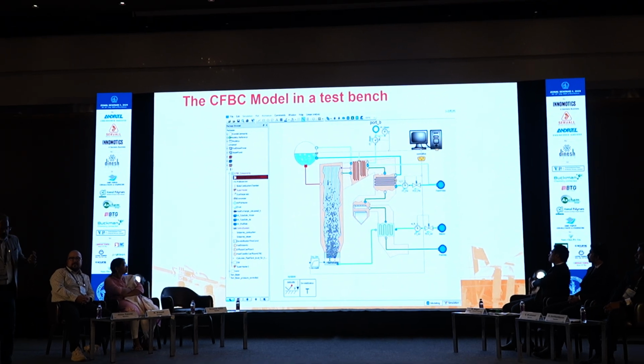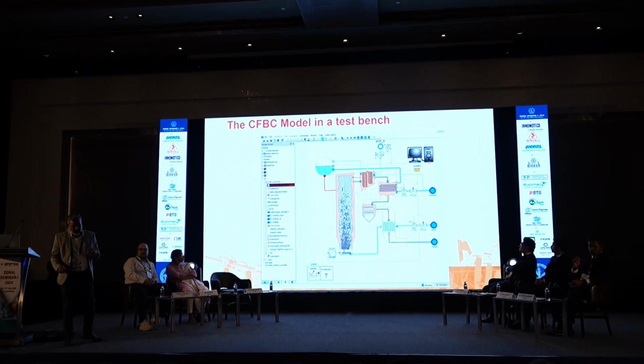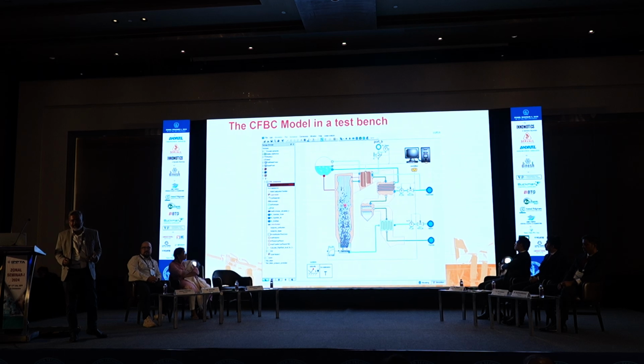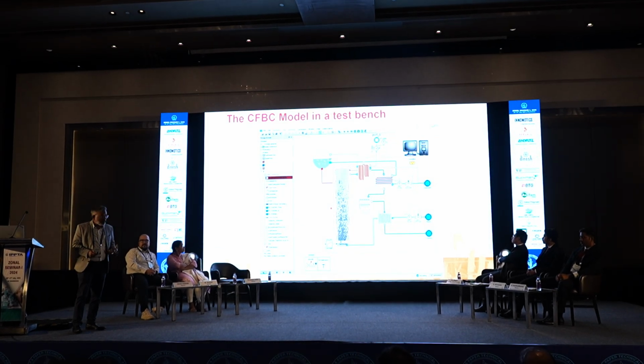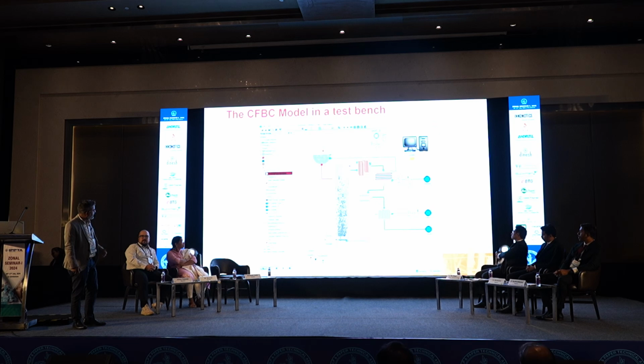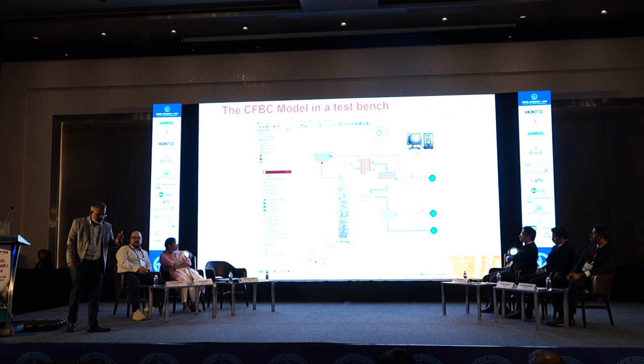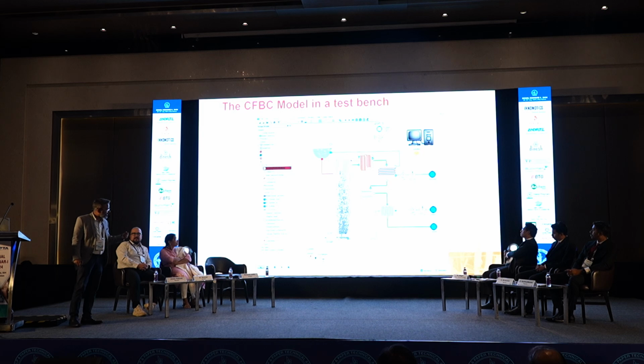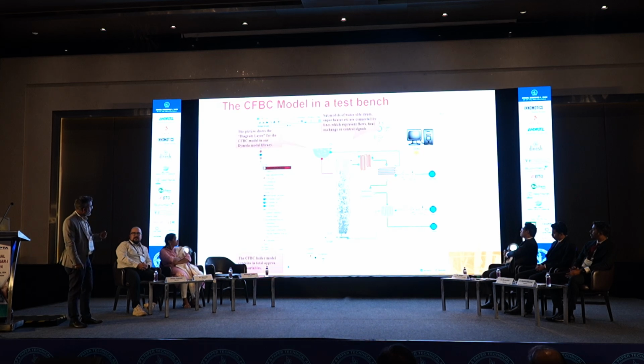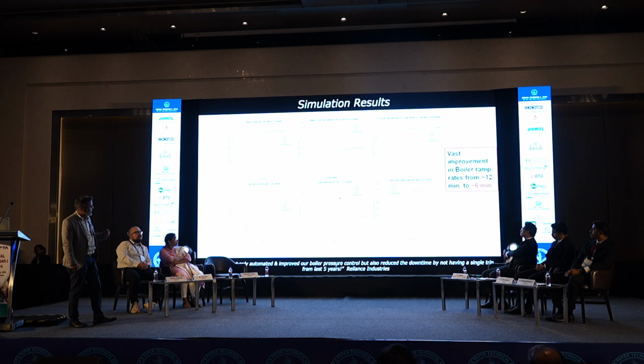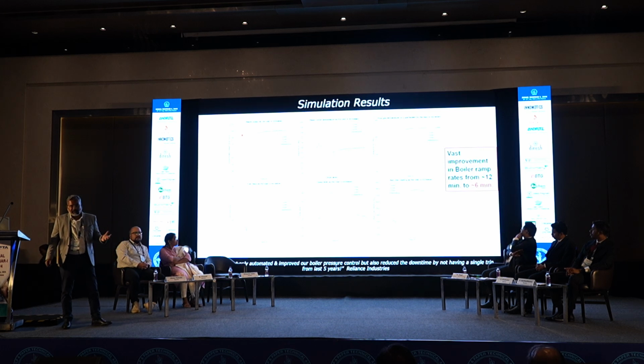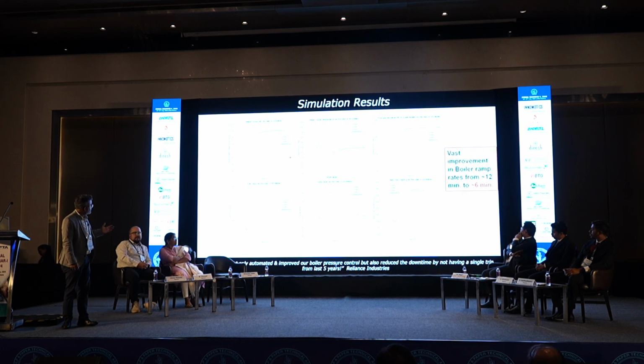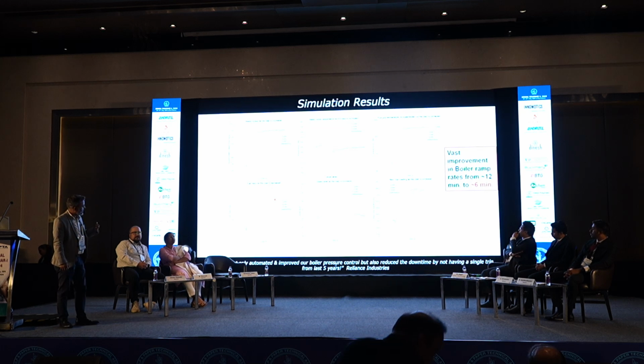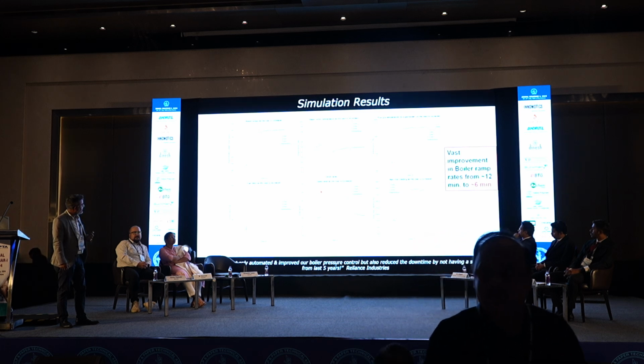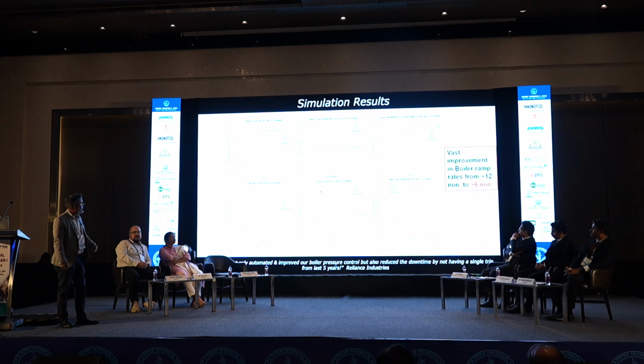So that was one challenge, how the boiler ramp rates can accurately be analyzed. So we developed a detailed model of the boilers, including superheaters, economizer, air preheaters. Around 3,500 variables were modeled in that. And when we simulated the whole scenarios, we came up with these results, which answer how my steam output will behave as the load is increased, how the steam outlet temperature will be as the load is increased, flue gas temperature, and so on.